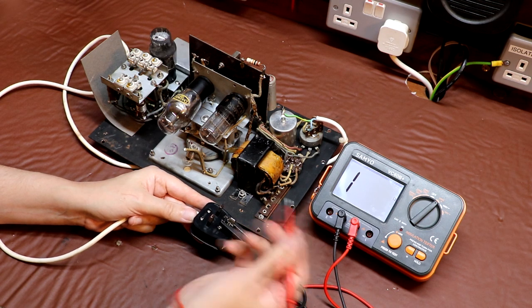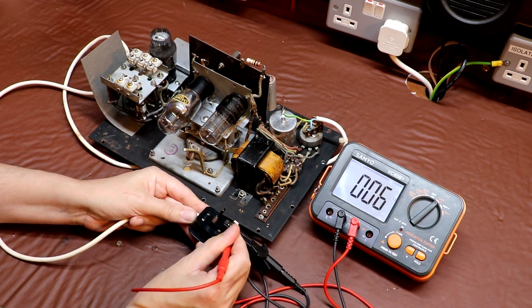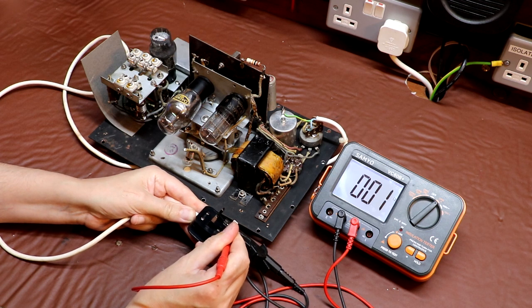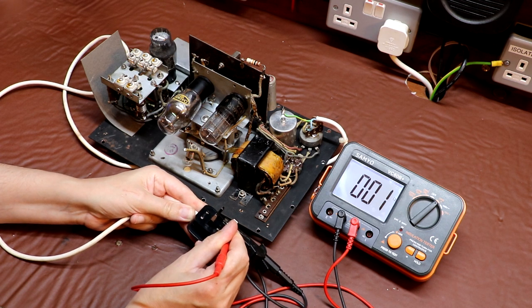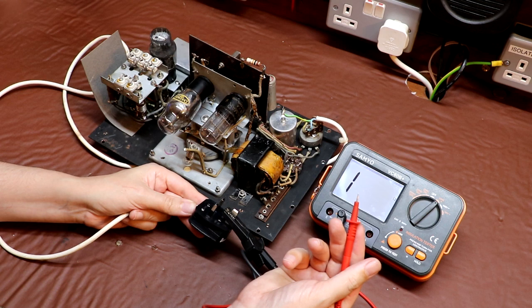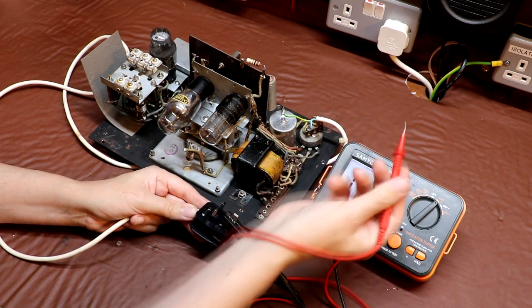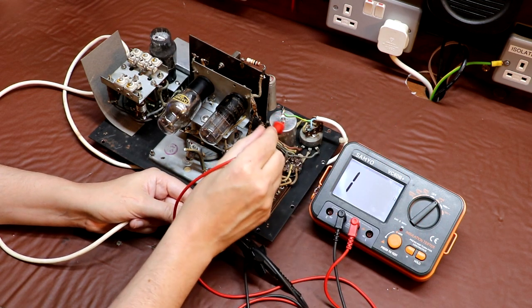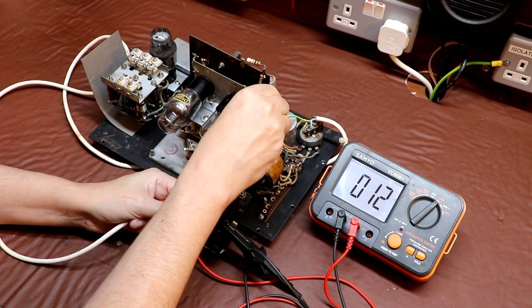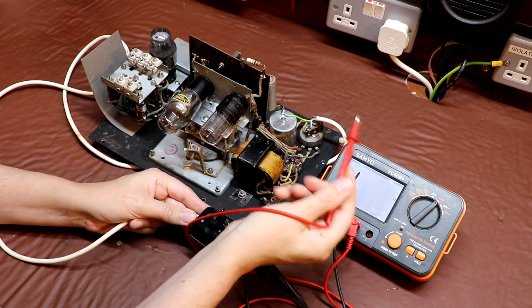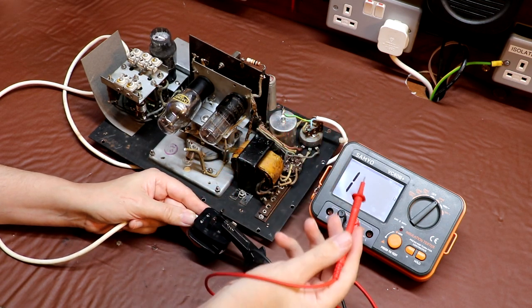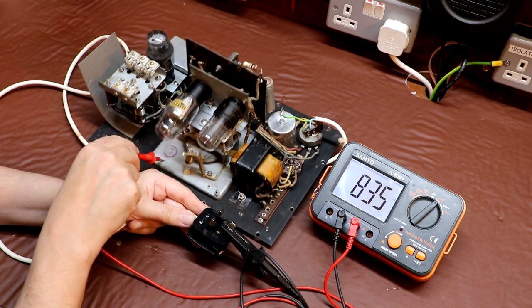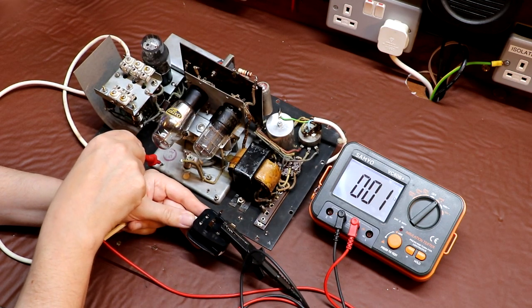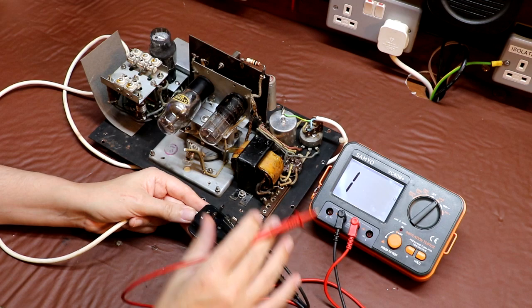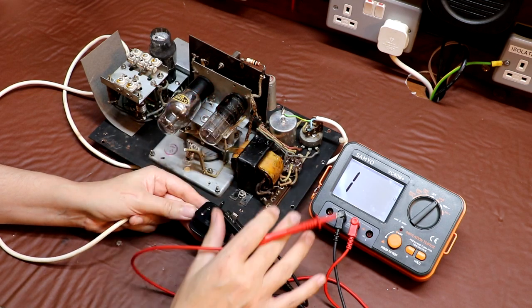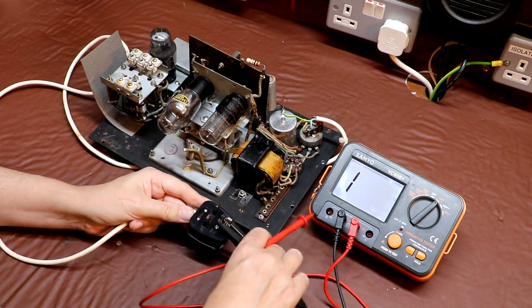So I'm going to start off by just getting a reading for the pin itself here. So we've got 1 ohm there, so it looks like the resistance in my leads here is about 1 ohm. Let's go to the actual incoming earth cable here where it's bolted to the chassis. Okay, still says 1 ohm, so we've got a nice low resistance. Let's try another piece of metalwork. And again, 1 ohm. So that proves that this piece of equipment is satisfactorily earthed at the moment.